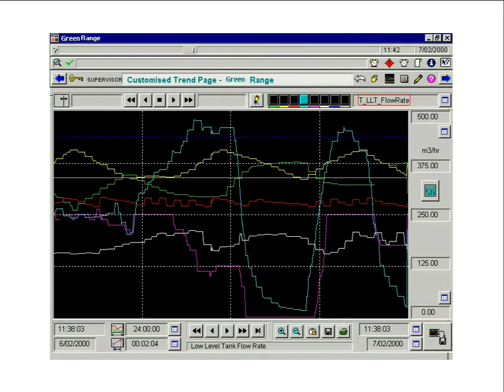We are dealing with that in terms of these are volumes of data. How do you deal with the backup systems? So what you'll find is there's a lot of redundancy in there. So at one time it would typically have the online system, a hot system, so it's getting all the data in the same real time, and maybe a cold standby system. So you've got 3 levels. Quite often it's 4 levels now. So you've got maybe 2 and 2 working together, and that's again another thing that a data historian can give you access to, because that's another way of holding the data, and you could port the data back into your SCADA system if you needed it.